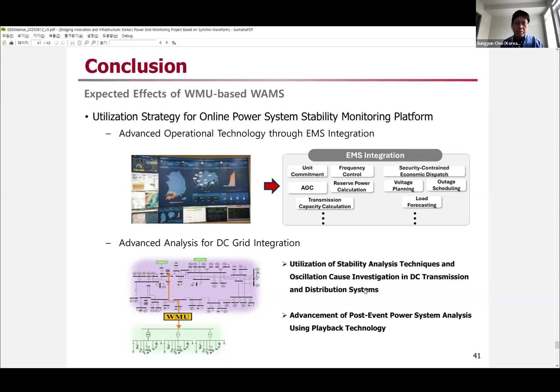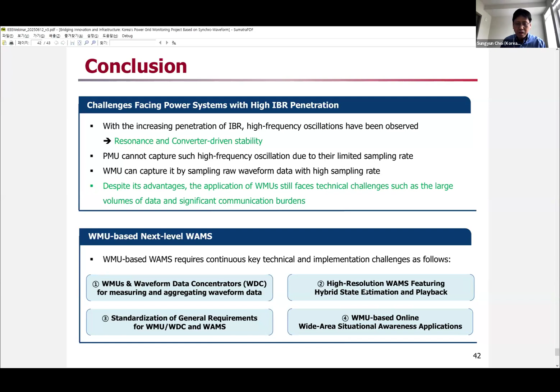This is the conclusion of my presentation. With high penetration of IBR, high frequency oscillations will be generated, and PMU and legacy measurements like PMU and SCADA cannot capture these high frequency oscillations. So we're going to use WMU, but it still has challenges, such as addressing large volume of data, communication burden, and standards. Finally, we're going to develop this WMU-based next level WAMS for these key technical challenges. That's all I have today. If you have any questions, I'm happy to answer.